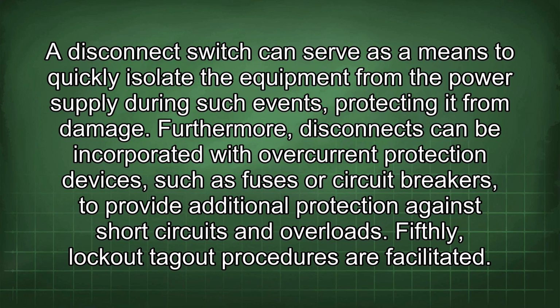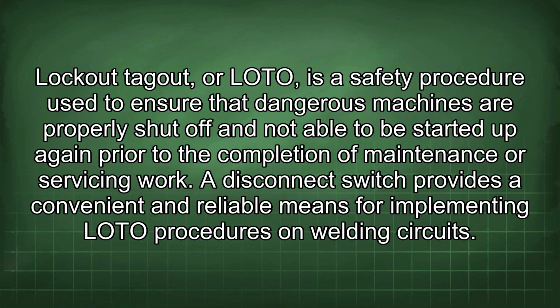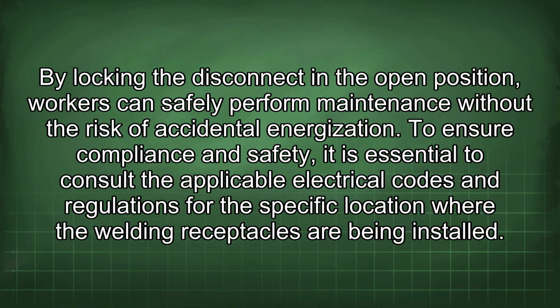Fifthly, lockout-tagout procedures are facilitated. Lockout-tagout, or LOTO, is a safety procedure used to ensure that dangerous machines are properly shut off and not able to be started up again prior to the completion of maintenance or servicing work. A disconnect switch provides a convenient and reliable means for implementing LOTO procedures on welding circuits. By locking the disconnect in the open position, workers can safely perform maintenance without the risk of accidental energization.